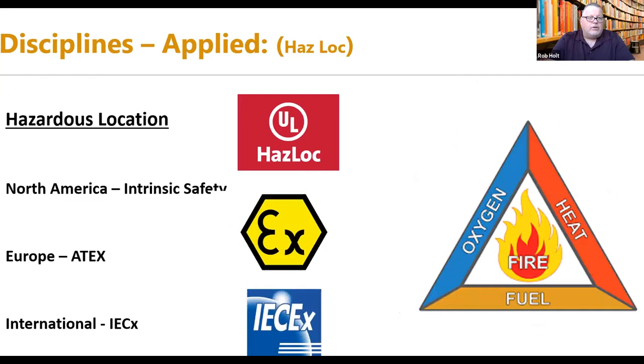For products going into a hazardous location, there's a similar approach to product safety. North America has intrinsic safety requirements, Europe has an ATEX program, and internationally there's IECEx. You can work with a Hazloc test lab or a consultant to plan for this, do one suite of testing, and come out with a certificate. You can also go the enclosure route, but there's still work to prove that even within the housing you're safe in these hazardous environments.